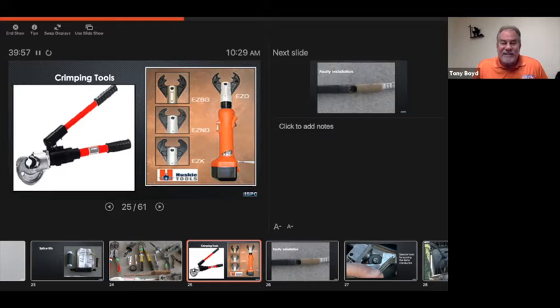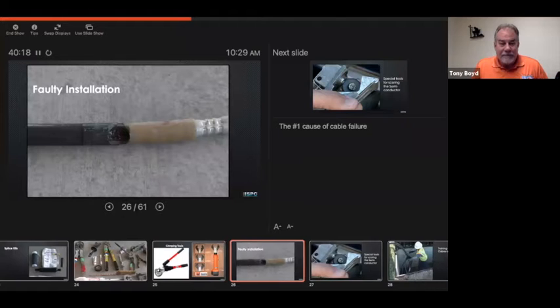Some of the important distinctions when making crimps is, depending on the type of die that you're using, you may have to rotate the press to keep the lug itself from what we call bananaing, getting a bend in it. So you always want it to maintain straight, and it's because of those stress lines that I talked about earlier.